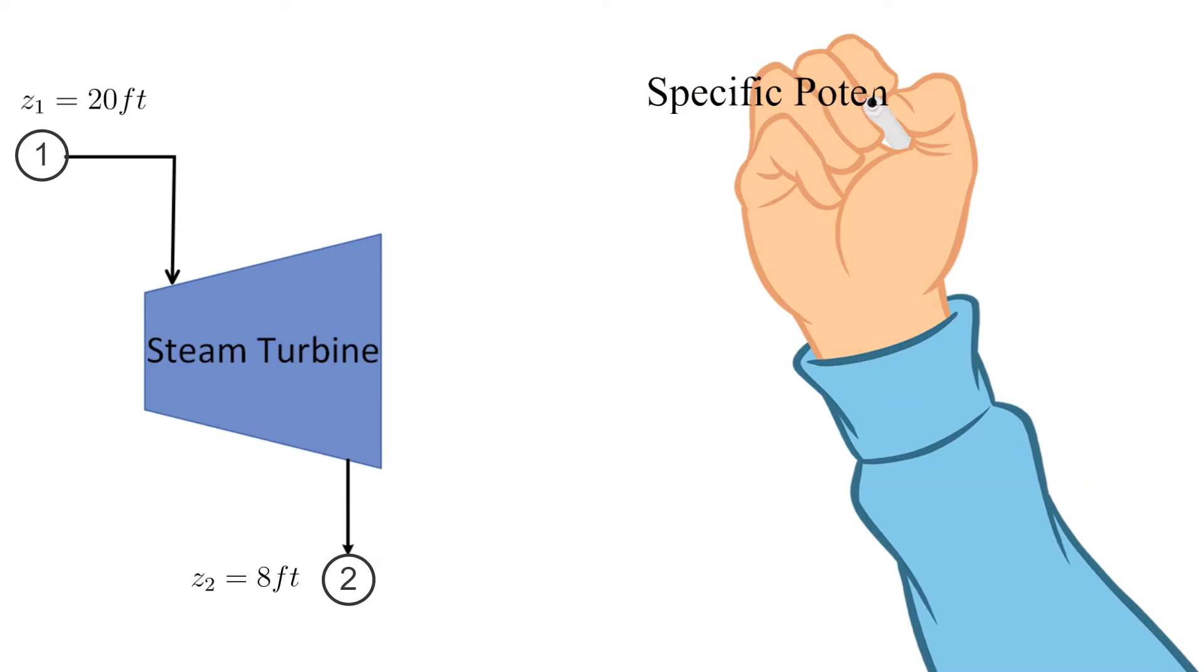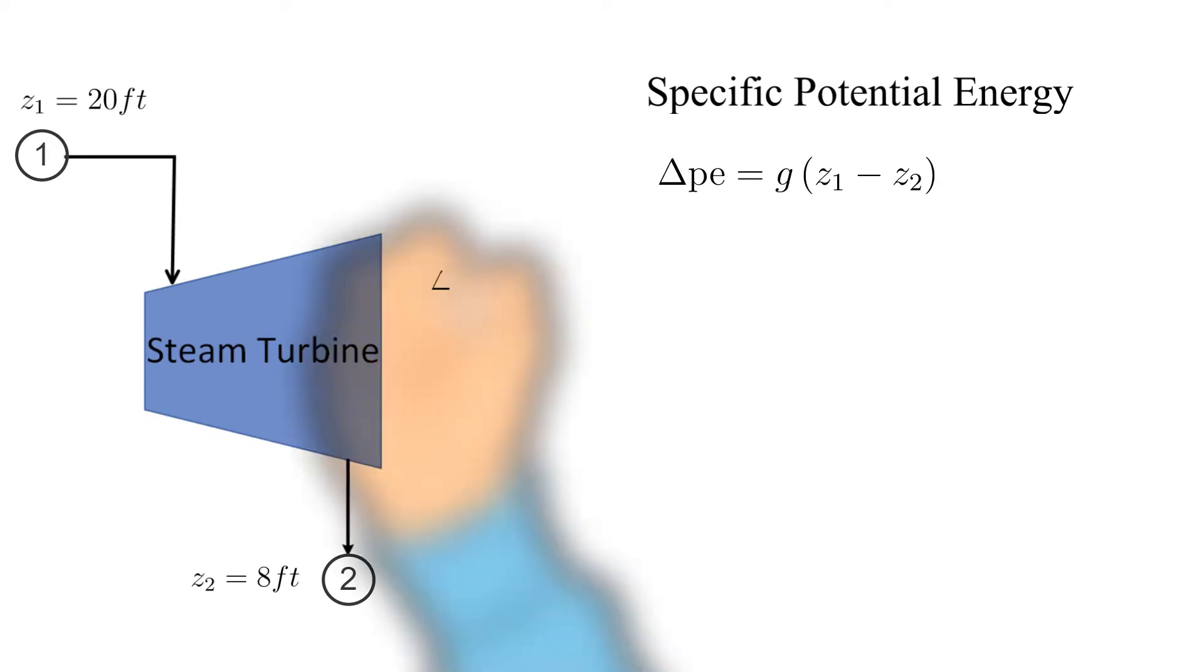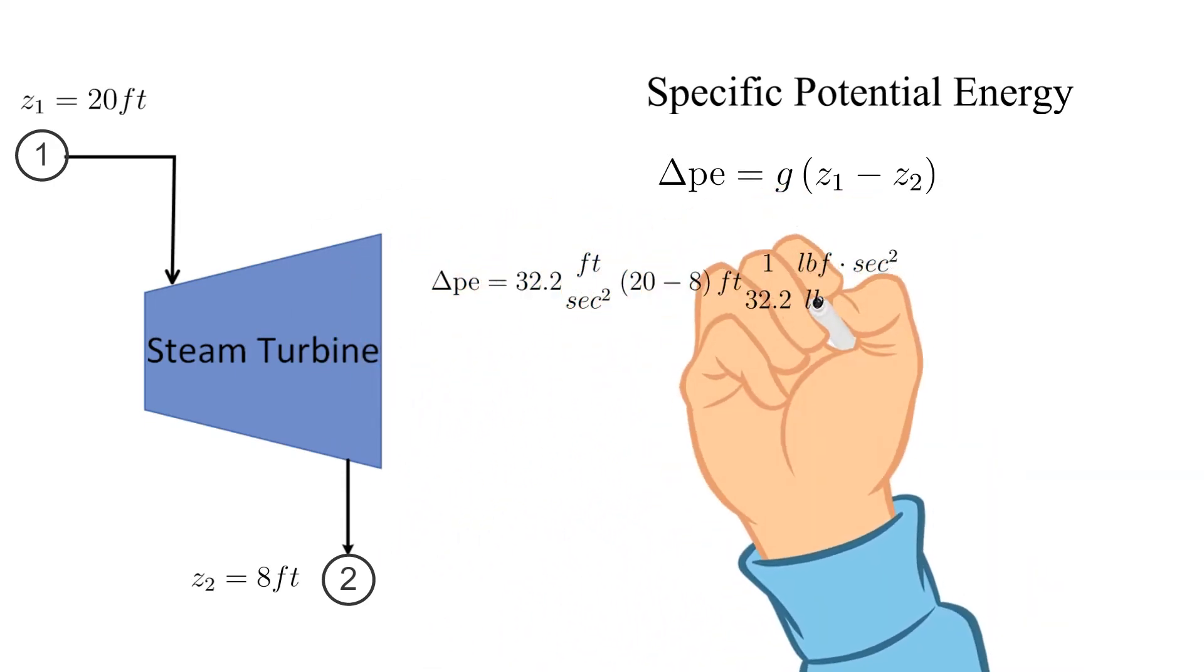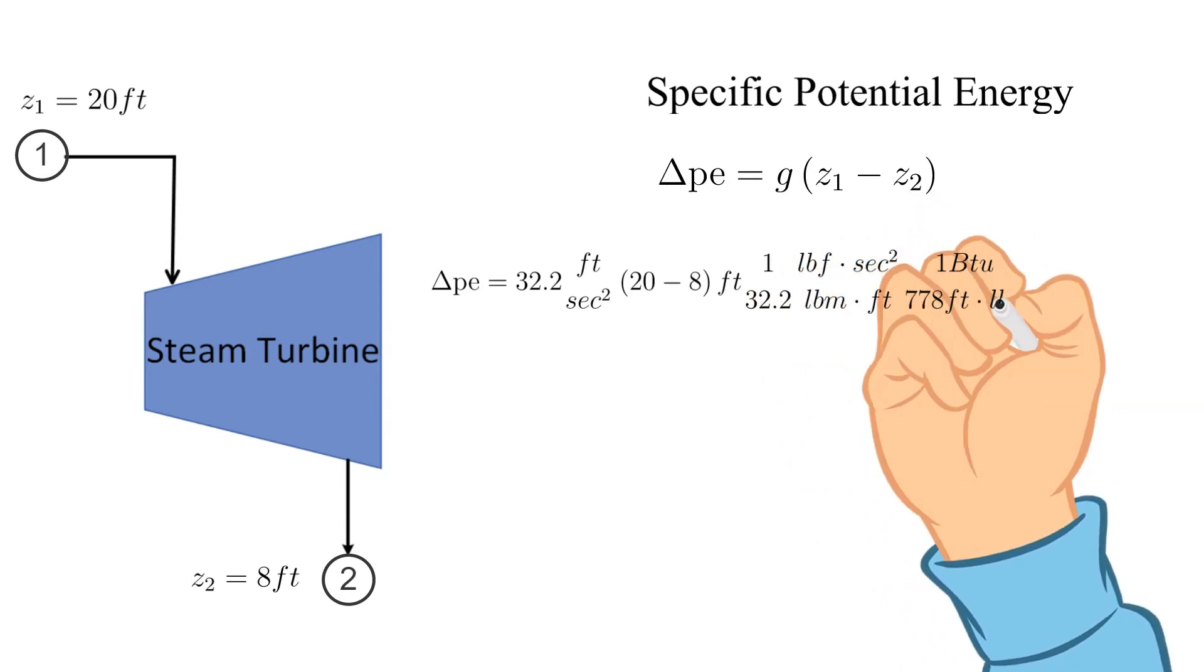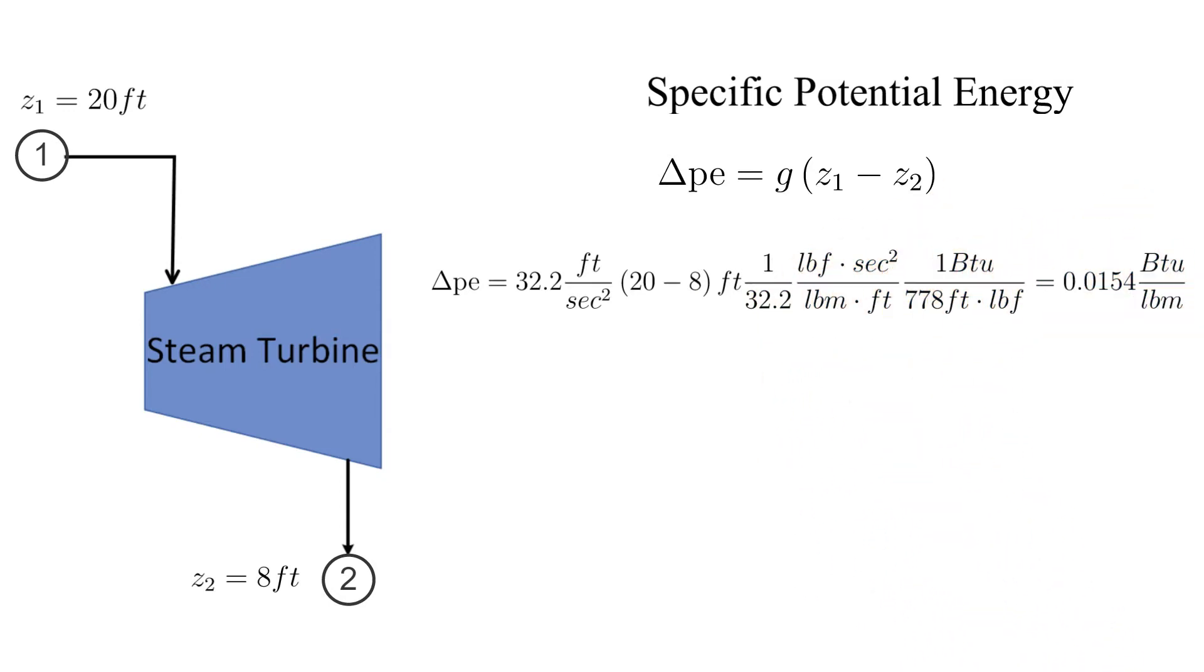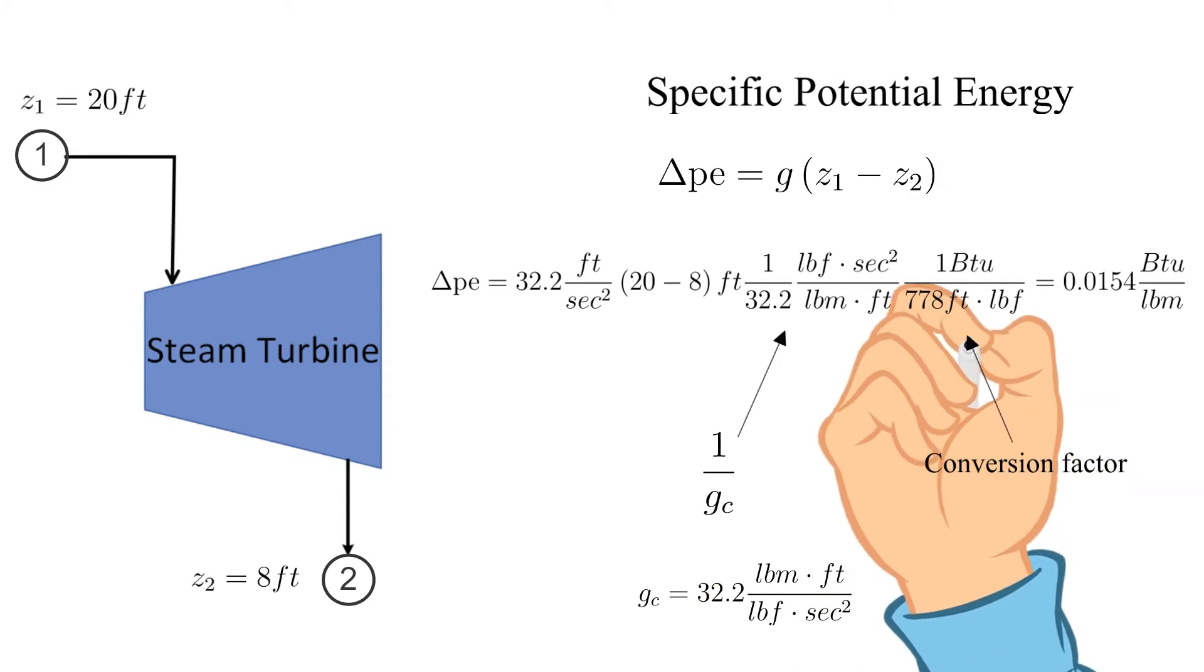Next is specific potential energy. Although multiplying the acceleration of gravity, g, times the elevation difference is a simple equation, it is fairly involved to achieve the desired units. Note the use of the gravitational constant, g_c, or more appropriately 1 over g_c. We are also converting from pounds force feet to BTU. For all that work, we get a pretty small value for the change in potential energy across the turbine.